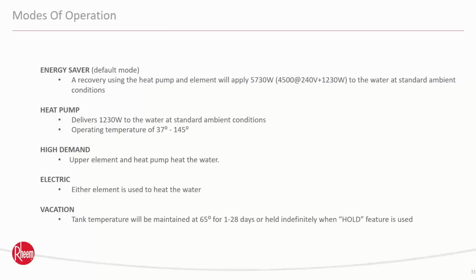So if you're a couple or a family that once you leave in the morning, nobody needs hot water all day long, nobody's at the house, put it in heat pump mode. This thing draws less than 3 amps. That compressor draws less than 3 amps. So it's pennies a day to heat that tank back up. So that's going to be your most efficient.